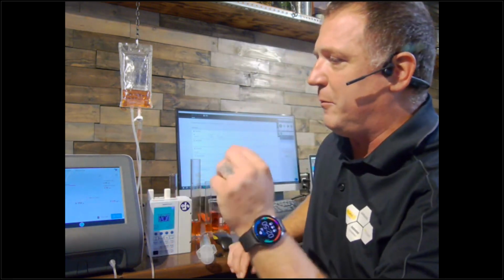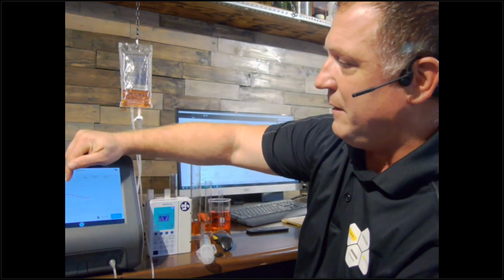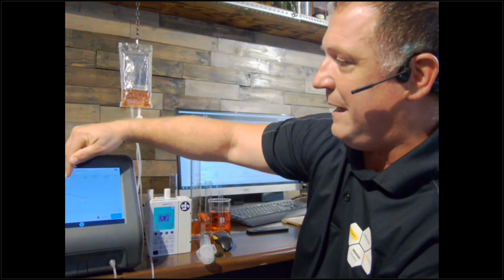If you're partway into a test, which is what I recommend, you can look at the waveforms it produces by pumping and actually see when the peristaltic pumps are resetting. If you looked closely at my screen in that video, you'll notice my IV pump has a bad finger in it, so there's a dropout every time it pumps. I can go into that flow, observe it, and look at any specific point in time by touching the screen to see the time and the exact average and instantaneous flow at that moment. This is great not just for biomeds and ISOs, but also for R&D folks designing new pumps or new applications. It's easy to use.